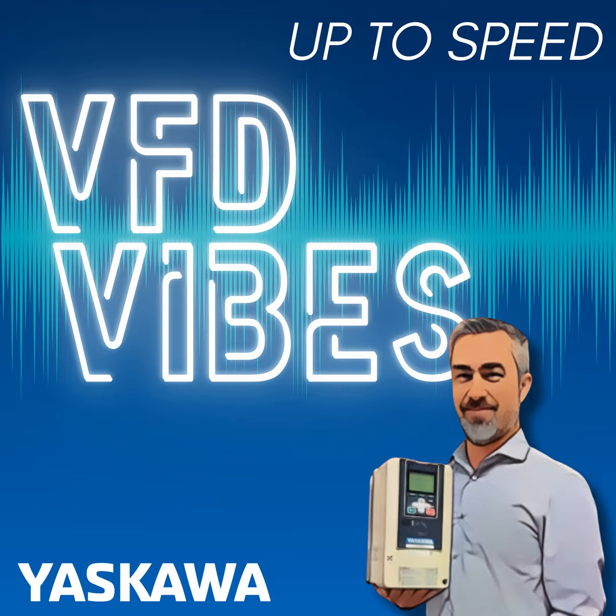You need to make sure it's built to handle the PWM voltage a VFD sends out. Voltage coming from the electrical grid is a nice clean sine wave. But if we remember how a VFD works, it takes that AC voltage, rectifies it into a DC voltage on the bus, and then recreates a sine wave on the output or inverter side of the drive. That is a simulated sine wave that we refer to as pulse width modulation.